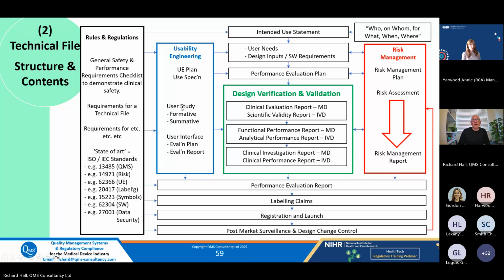You must do some form of clinical evaluation for medical devices or scientific validity report for an IVD. Now, a clinical evaluation report is a combination of both the clinical investigation for medical devices and a literature study, whereas the scientific validity report is just a literature study. But they both have to be done. I gave you the MedDev for the CER in the previous slide. I'm trying to remember now, 2.7/1 revision 4, I think it is. Functional performance report or analytical performance report, they call it for IVDs.